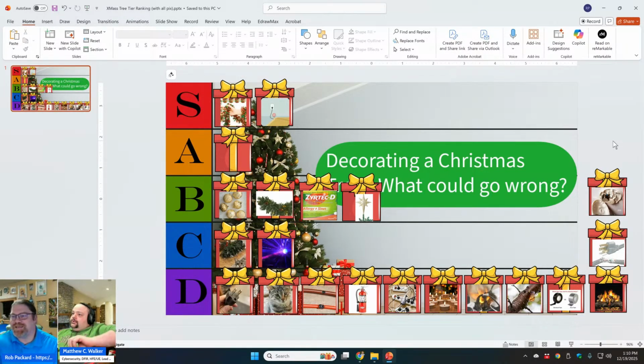So that's our list. A general rule of thumb is that the FDA requires validation testing for everything associated with a critical task. Based on the ranking of our hazards here, if the use error is going to almost all of these, we're looking at a large series of critical tasks. I don't think this medical Christmas tree is going to be the type of device that gets to submit its regulatory submission without performing usability testing.